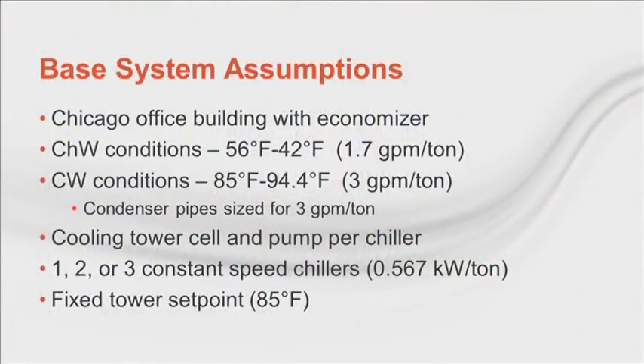in the system. Shown here is our base system configuration for the office building in Chicago. The building has an air side economizer, so during many hours of building operation, the chilled water plant will be off. Note the design condenser water flow rate of 3 GPM per ton is something we'll reconsider, as are the chiller type and the cooling tower set point. Since we often see building operators use a fixed set point, our base reflects that.